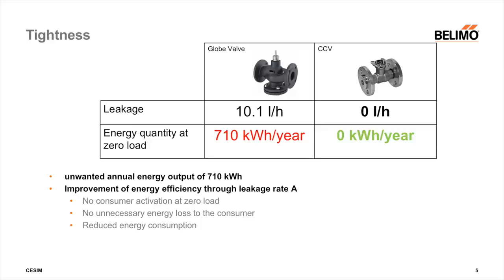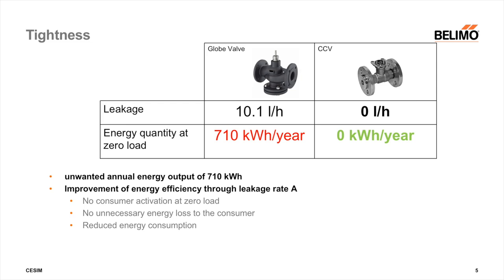As we have already learned about energy efficiency from another module, this energy loss of a globe valve can be calculated and it can be quite high. In this example, we have a leakage rate of this globe valve of 10.1 liters per hour, which leads to an energy quantity at zero load every year of 710 kWh. In comparison, a characterized control valve from Belimo has no consumer activation at zero load, no unnecessary energy loss to the consumer, and therefore reduced energy consumption.